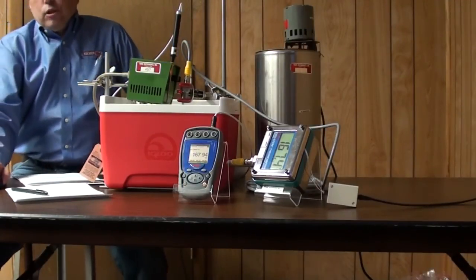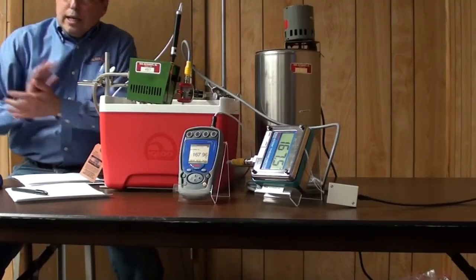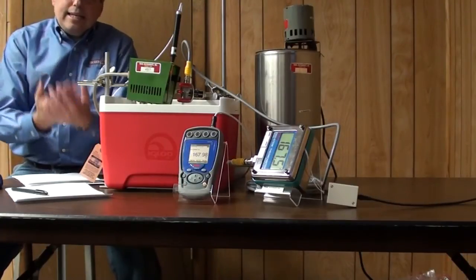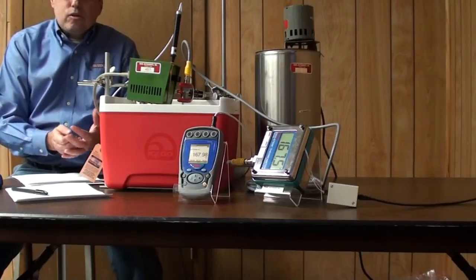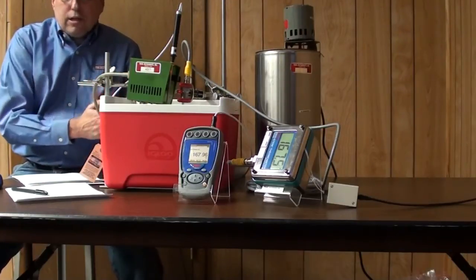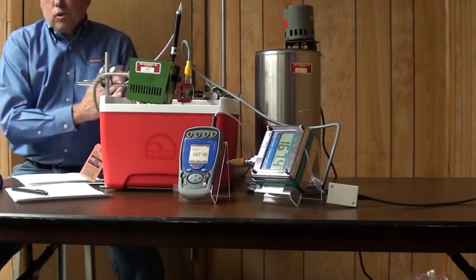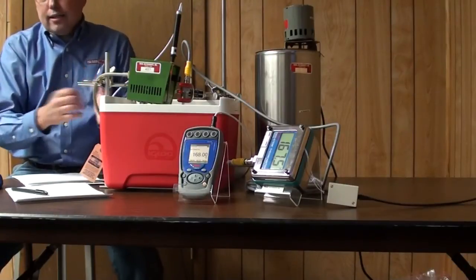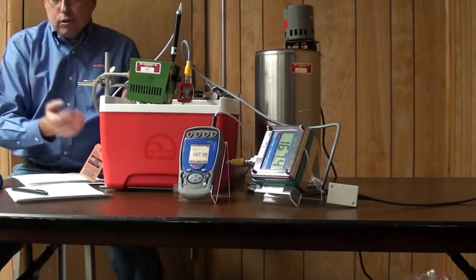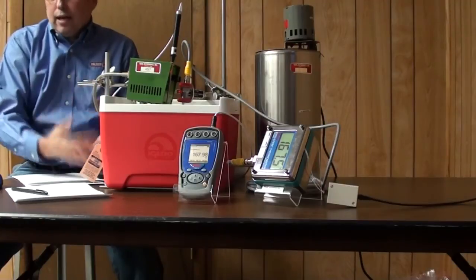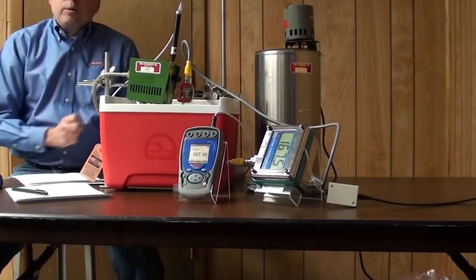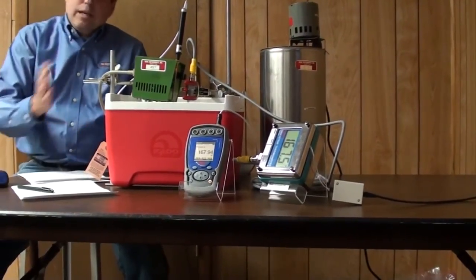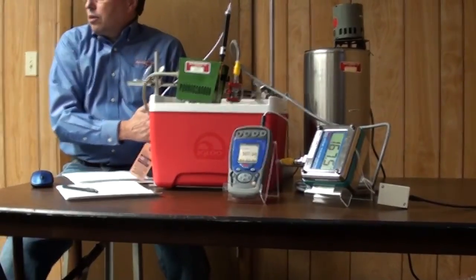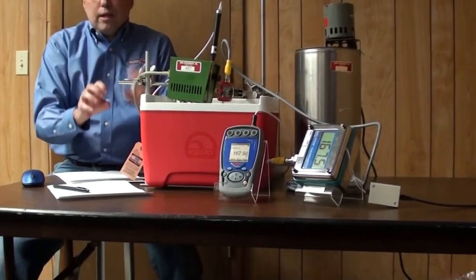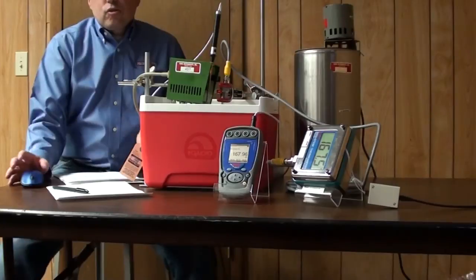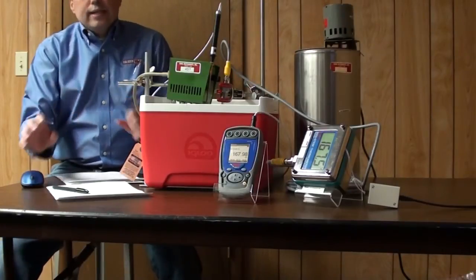So once you calibrate it, you need to label it. And certainly anytime you're calibrating a device, that device should already have a calibration label on it. It will say that it's due July 18th, 2014, for example. When we calibrate that today, you need to remove that old label and then put on the new label. You don't want multiple labels on your devices with conflicting dates.